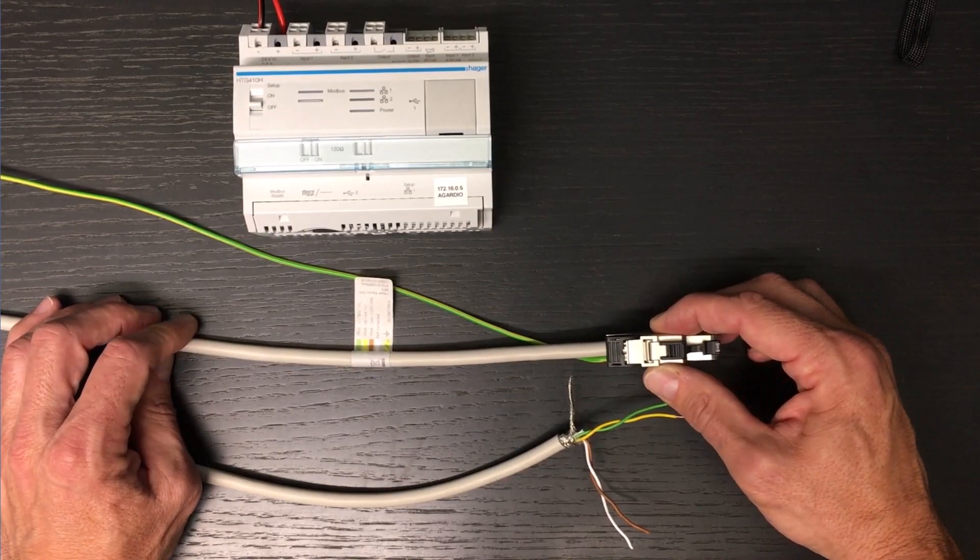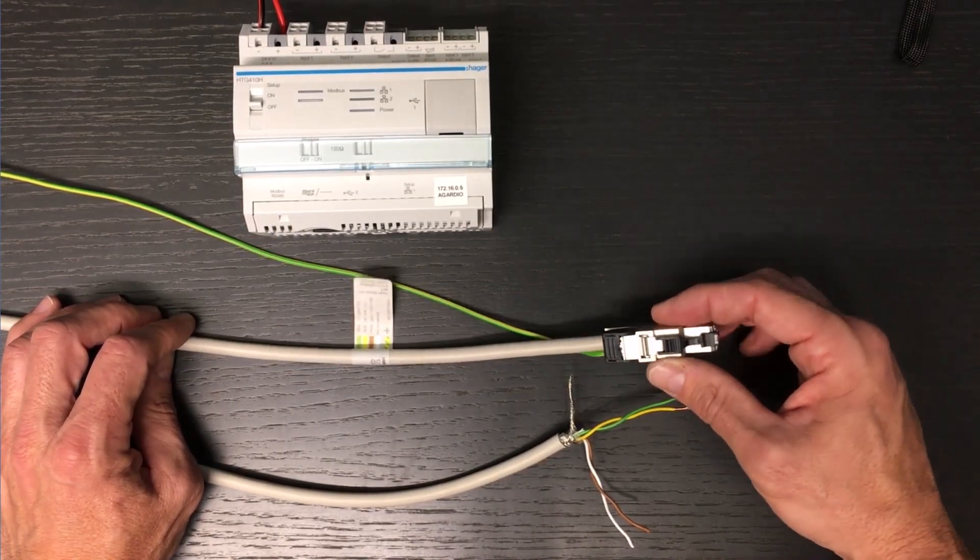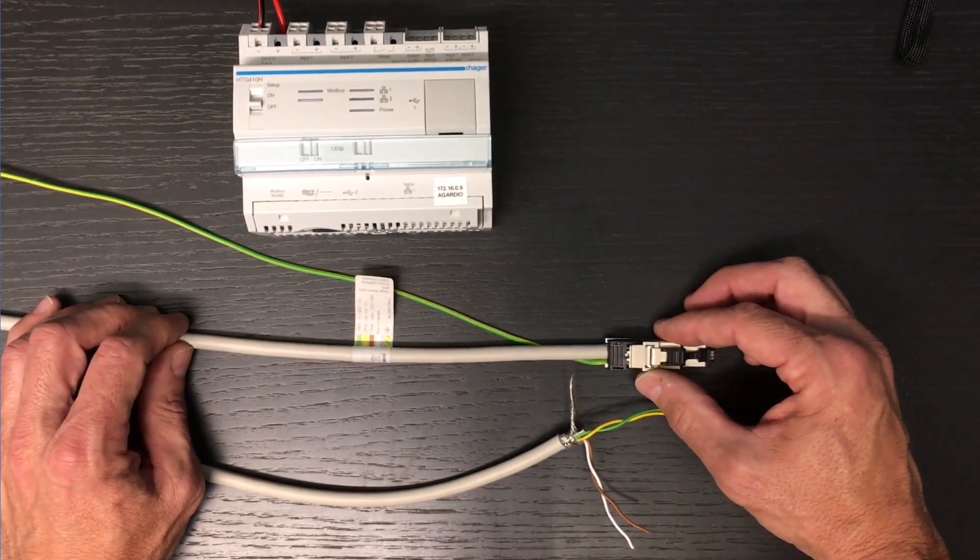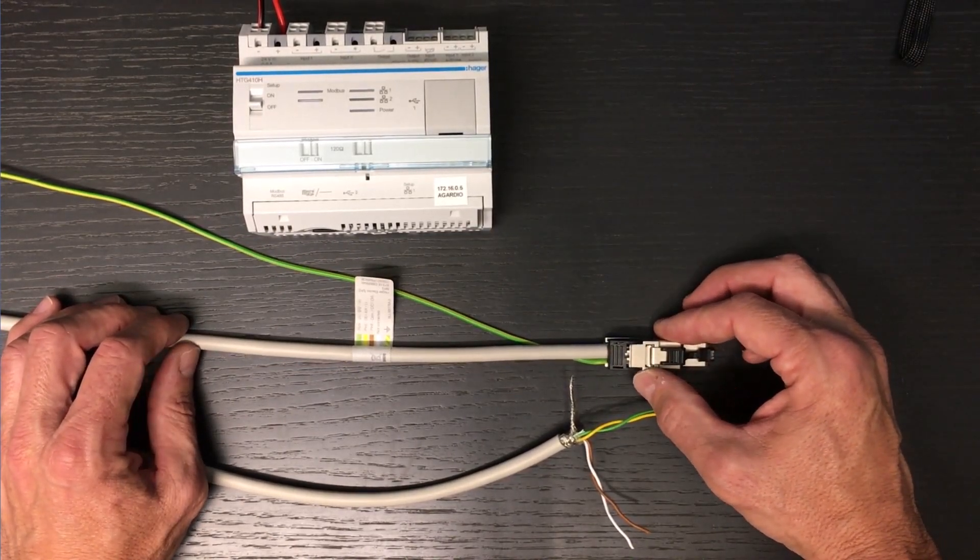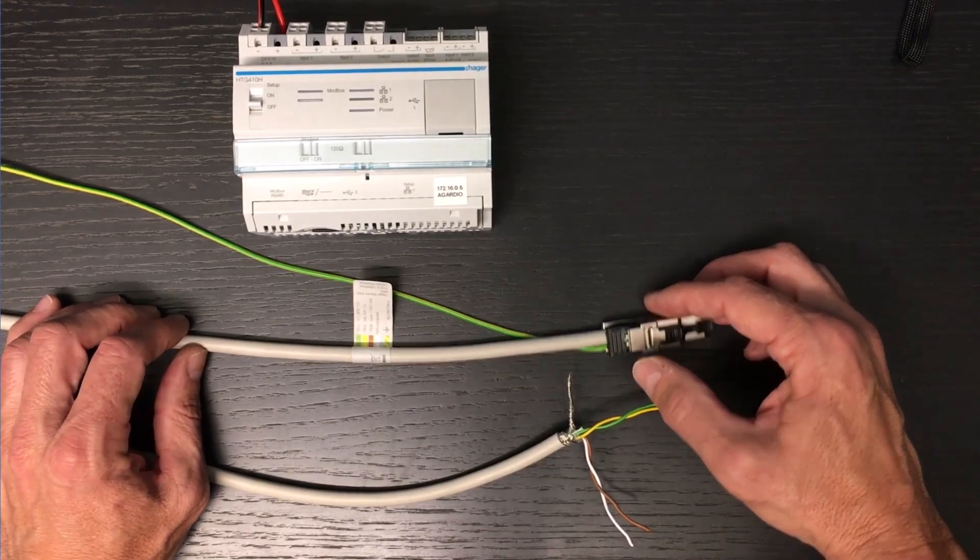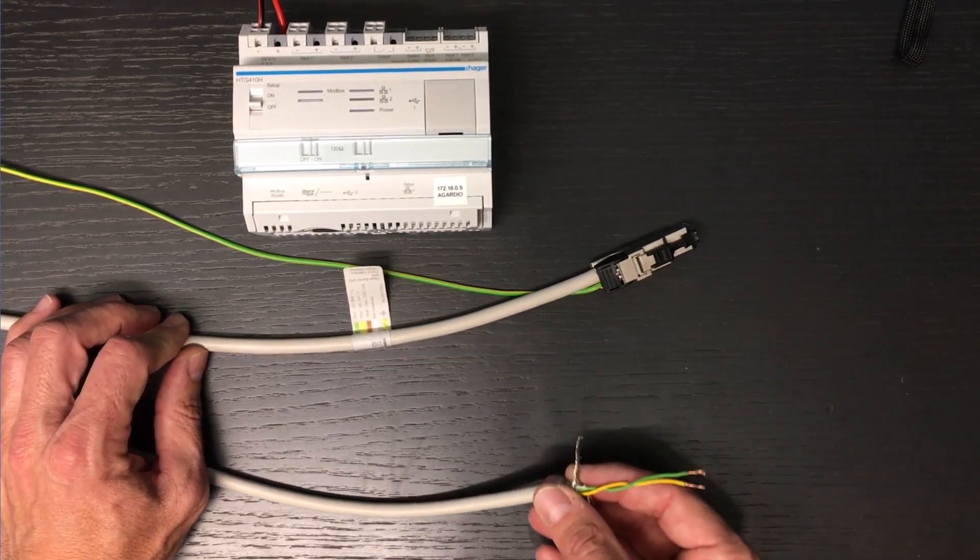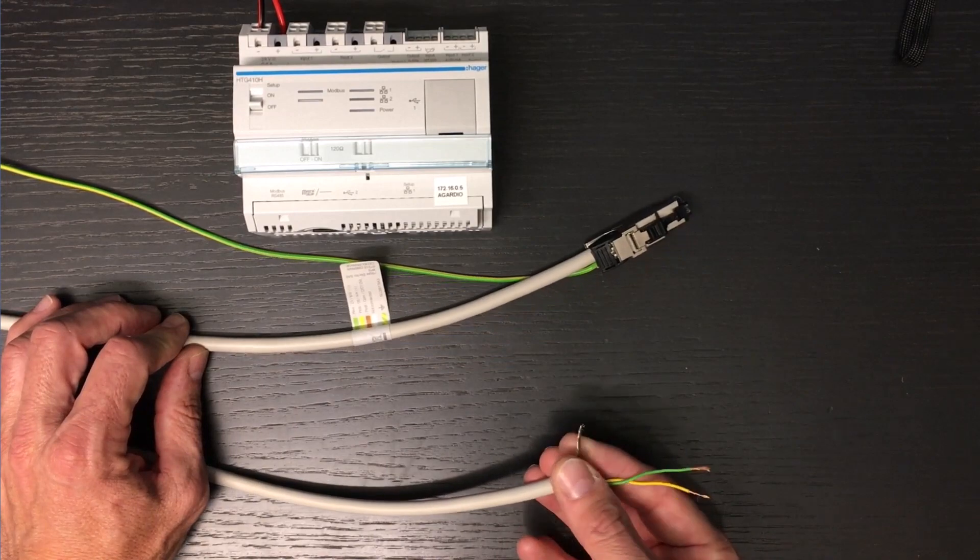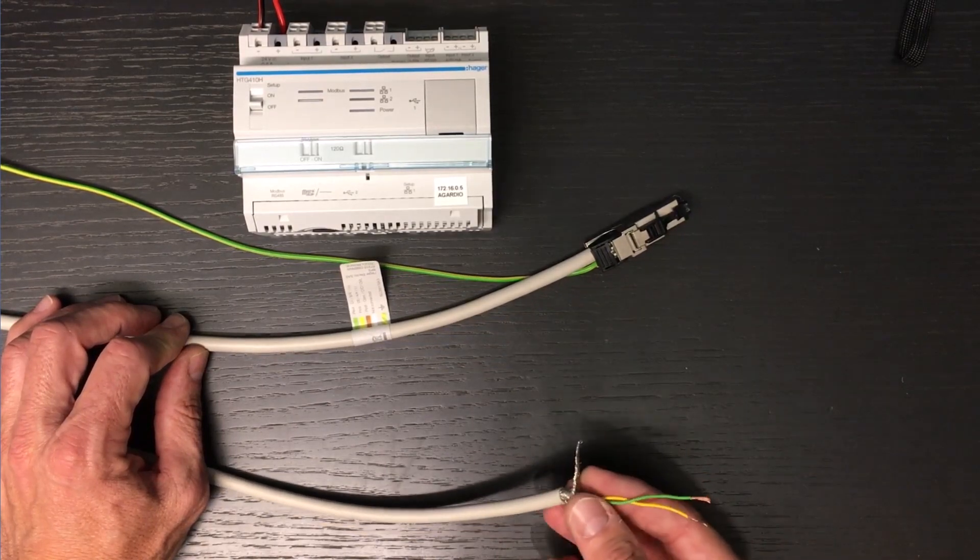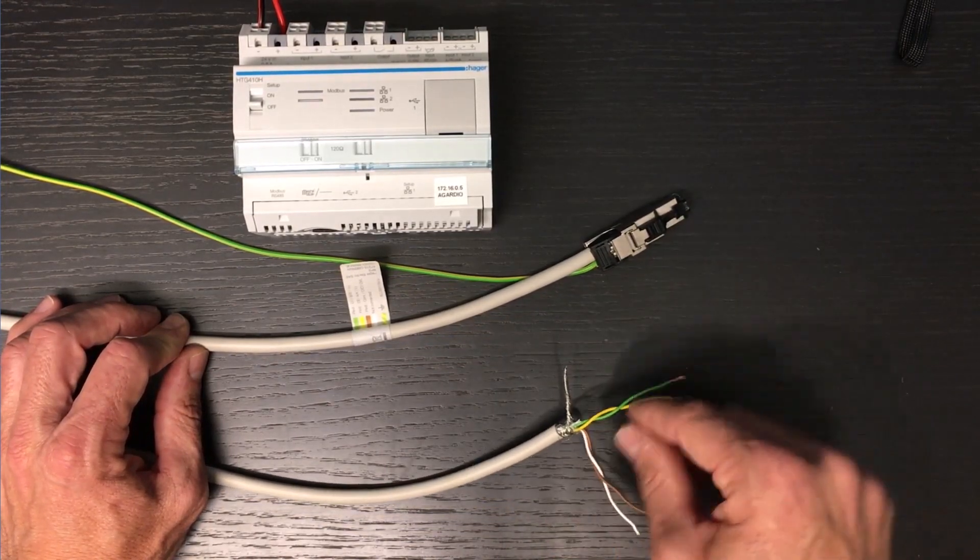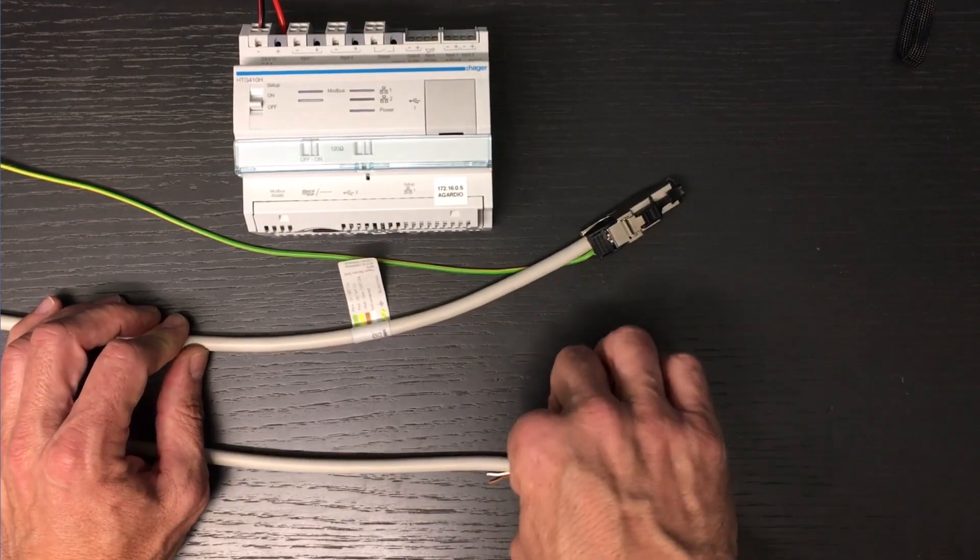The cable shielding of the first product must be earthed at one end only. At the other end of the cable is the shielding and the pair that is used for Modbus communication. Green corresponds to positive polarity and yellow to negative polarity. The other pair is not used on Agardio devices.